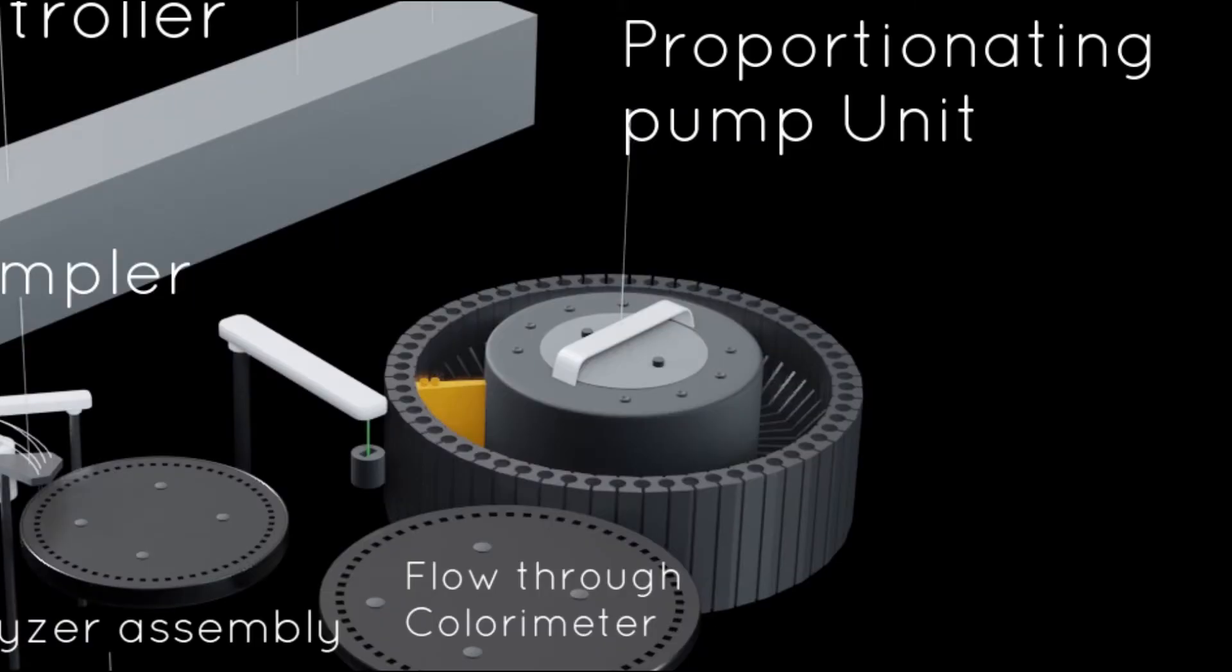The next component is the proportionating pump unit. This module determines the relative flow rates of sample and all reagents and replaces the use of different sizes of pipettes and manual methods.